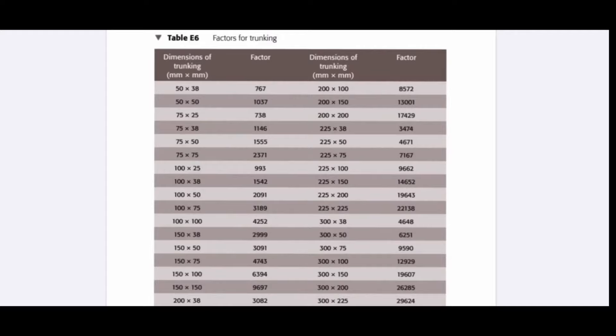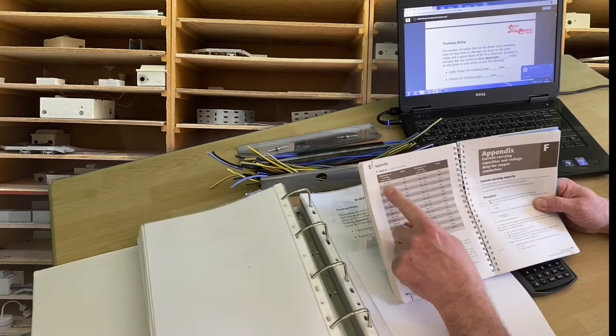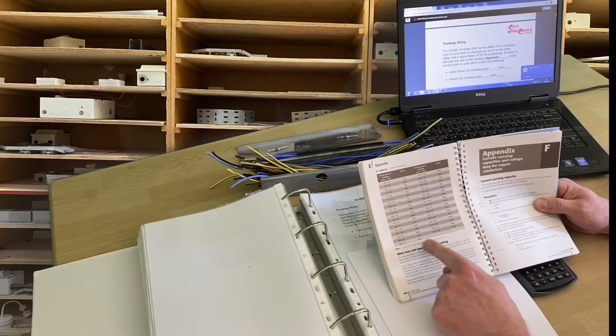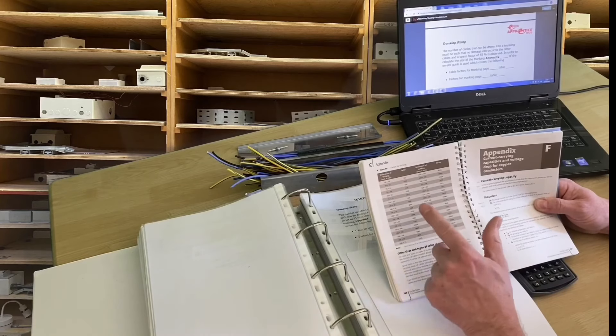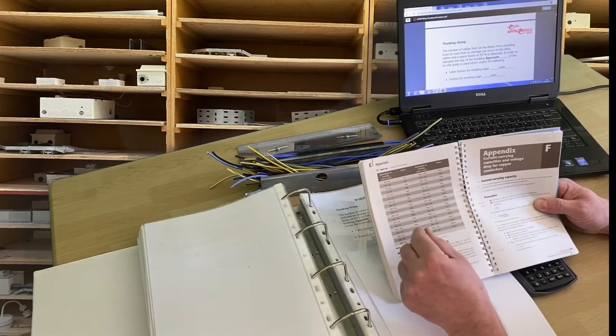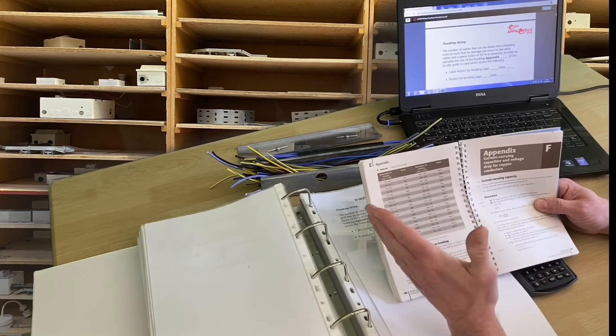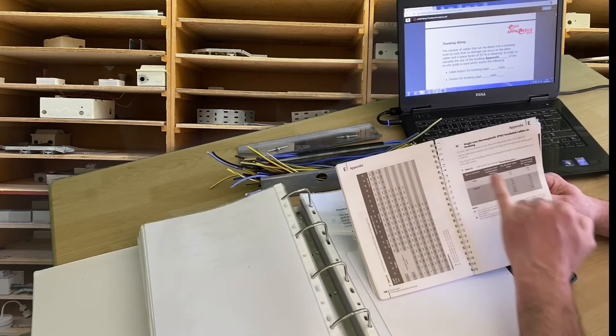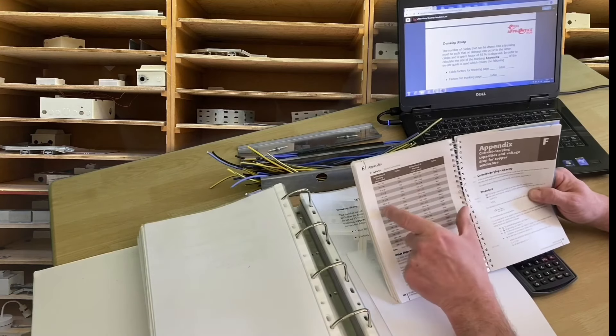The big difference with table E6 is that the factors are not in a logical order. For example, 50 by 38 has a factor of 767, the next one — 50 by 50 — has a factor of 1037, and then 75 by 25 has a factor of 738. So in the notes I expect you to find the smallest trunking available by scanning through the factors until you find the one that closely matches the factor generated by the conductors. Those are Appendix E tables E5 and E6.